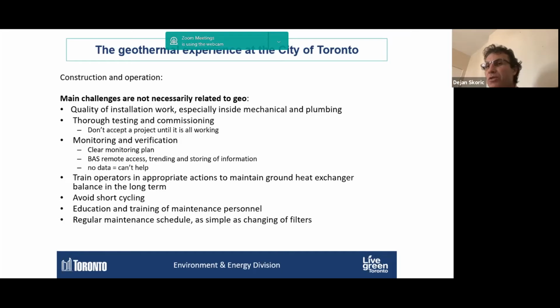We had issues where, if you have steel pipes inside with glycol, you need to have rust inhibitor. In one particular case, they didn't put in rust inhibitor, so our heat pumps blew up after two years because of all the gunk that built up in the pipes. Those issues have nothing to do with geo itself. It all comes down to the quality control and quality assurance of the project.